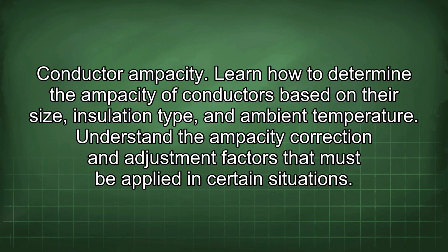Conductor ampacity. Learn how to determine the ampacity of conductors based on their size, insulation type, and ambient temperature. Understand the ampacity correction and adjustment factors that must be applied in certain situations.